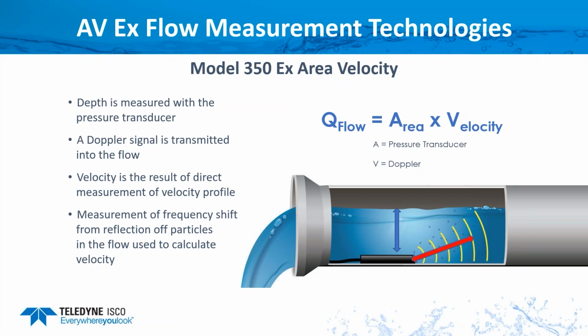And one question I get a lot is, well, what happens if the pipe goes surcharged or completely full? Well, your electronics are smart enough to know that you've hit 100% of the wetted area. And so then now we're just using the velocity proportional to flow to continue to give you accurate flow readings.